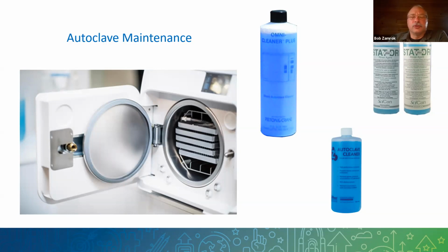There's also a series of filters on the sterilizers. If you have a Class B sterilizer like this Lisa, and Tuttnauer has them too, there are HEPA filters and air filters you have to replace at least once a year, and water filters inside as well. Some manufacturers make it easy to do that maintenance yourself in the office, while others require you to take covers off, which is more cumbersome. It depends on the device and how ambitious you are - just follow what's in the manual. Most of them are really good.